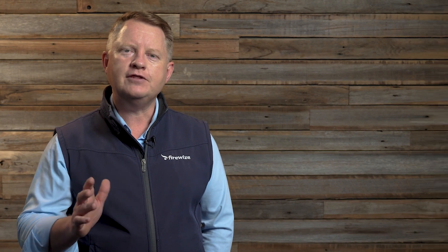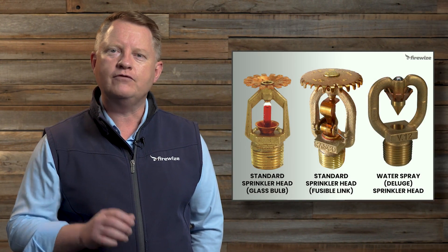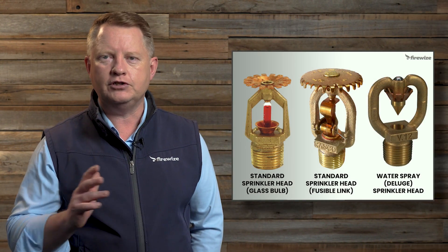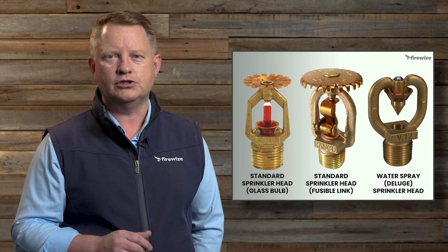A conventional sprinkler head is a type of valve that controls the flow of water to stop a fire. Unlike conventional movie wisdom, not all sprinkler heads operate at once, except for deluge type fire sprinkler systems used in special hazard applications, where the sprinkler system is designed for all of the sprinkler heads to activate at the same time. Check out the image on the right for an example of the visible differences between a conventional sprinkler head and a deluge sprinkler head.